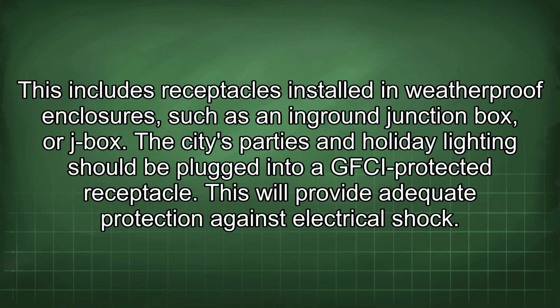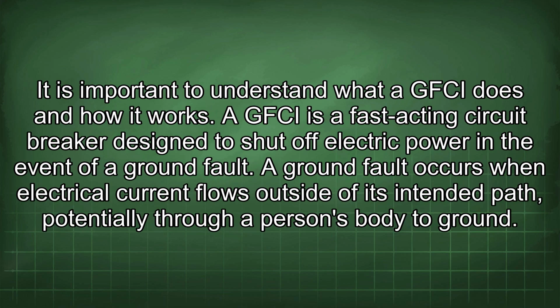The city's parties and holiday lighting should be plugged into a GFCI protected receptacle. This will provide adequate protection against electrical shock. It is important to understand what a GFCI does and how it works. A GFCI is a fast-acting circuit breaker designed to shut off electric power in the event of a ground fault. A ground fault occurs when electrical current flows outside of its intended path, potentially through a person's body to ground.